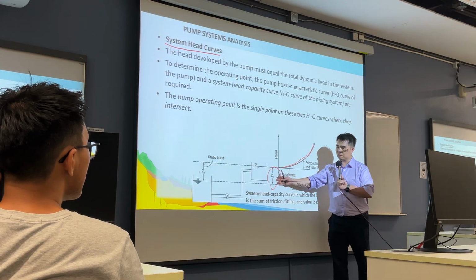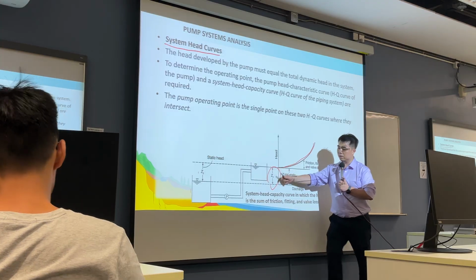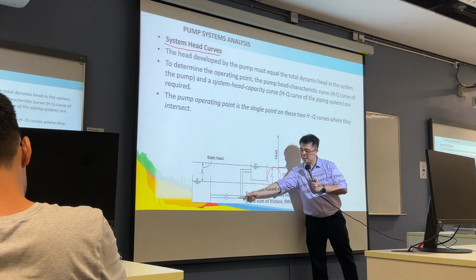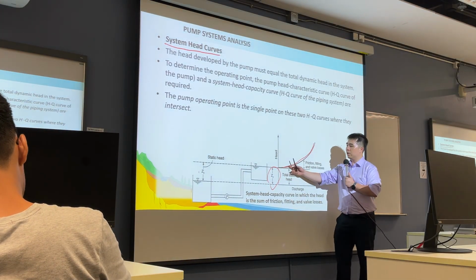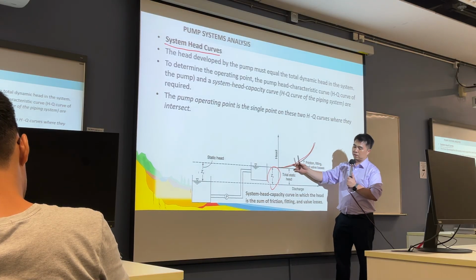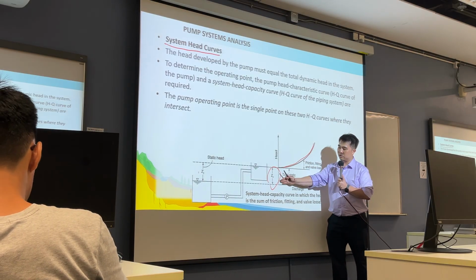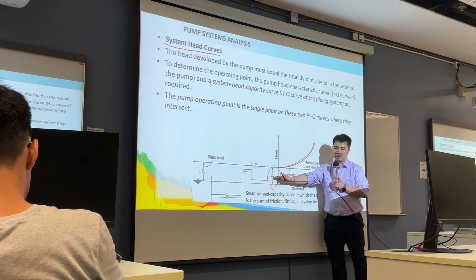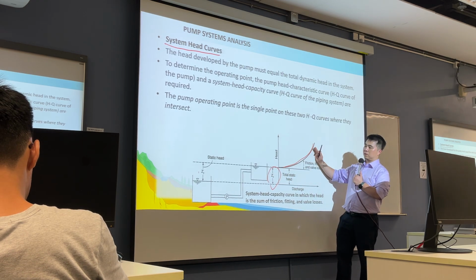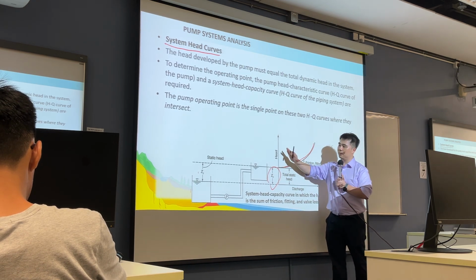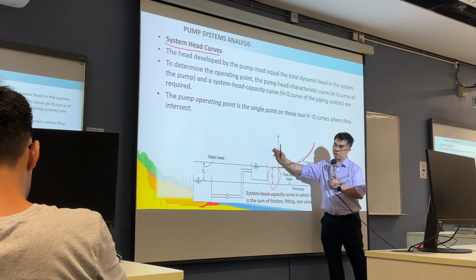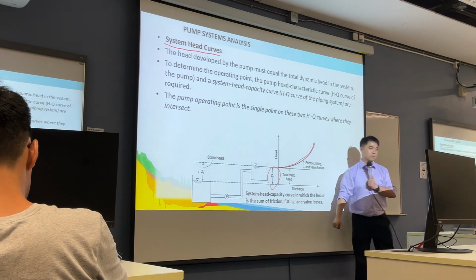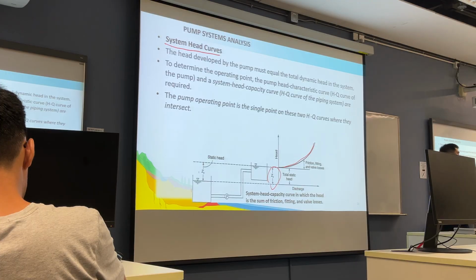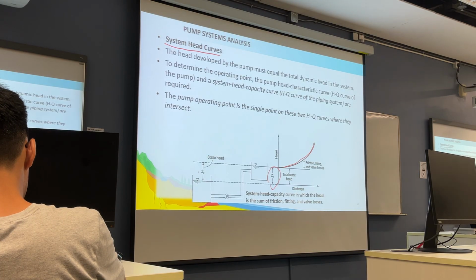The frictional loss and the component head loss, for example from the pipe and the fittings, will be proportional to the discharge, to the flow velocity, okay? So it is higher than the static head. If you pump the flow faster, you need to overcome more frictional and component head loss, okay? So the typical system curve is like this.